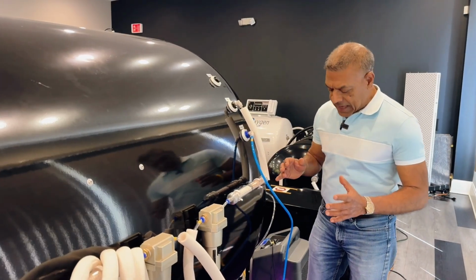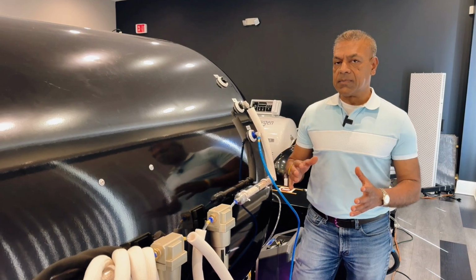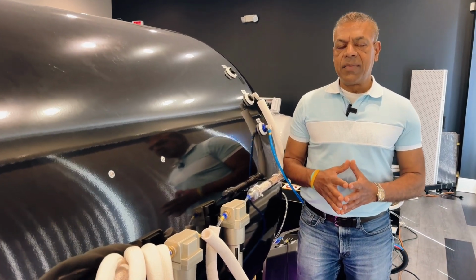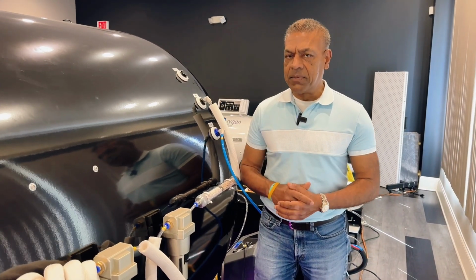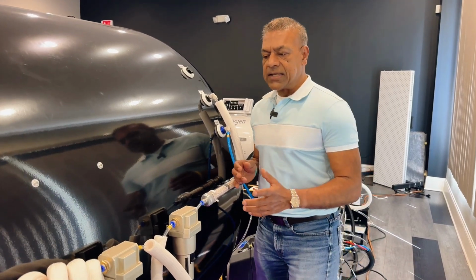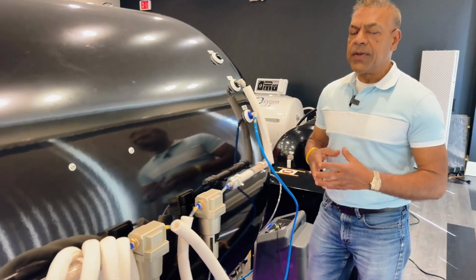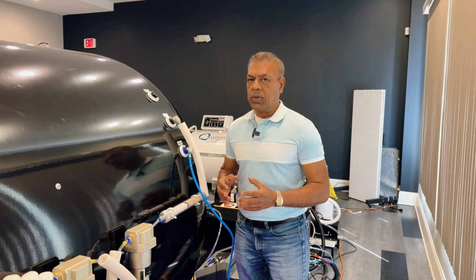Now, many of you have asked us the question of how to maintain this multi-place chamber. Of course, there are some maintenance variables involved, but they're quite simple. One of the things that you'd have to replace from time to time, usage dependent, I repeat, usage dependent, is the filter here and the filter here. Depending on how frequently you are using this chamber, you will have to replace the filter at some point in time. We do have qualified technicians who can come in and replace those filters for you, and then they will also do the pressure test and a few other tests along with the maintenance.